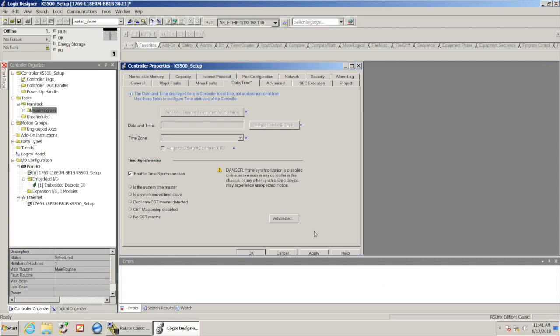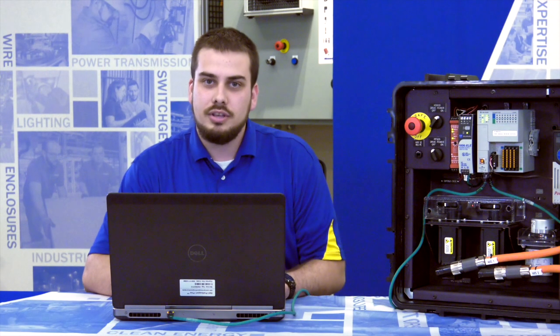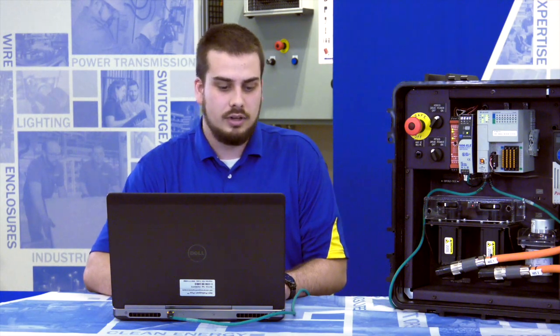The CIP Motion, the Ethernet servo drives, require that time synchronization so they timestamp the packets when they're sending them from the controller to the servo drives. So I just have to check that box and I can say OK. From there, there's a few other things I need to do to get this to work.